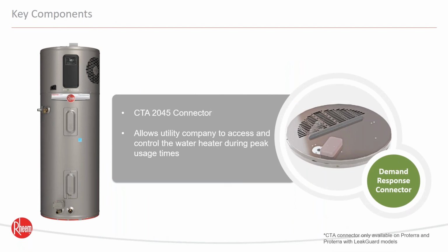We talked about utilities controlling these units as thermal storage devices. We have our EcoNet communications platform already built in, and we also have a built-in CTA 2045 connector. That way they can ship the homeowner a module and enroll them into a demand response program. They're going to get additional savings because they'll schedule this water heater around time-of-use peak rates, as well as provide high levels of consumer satisfaction.